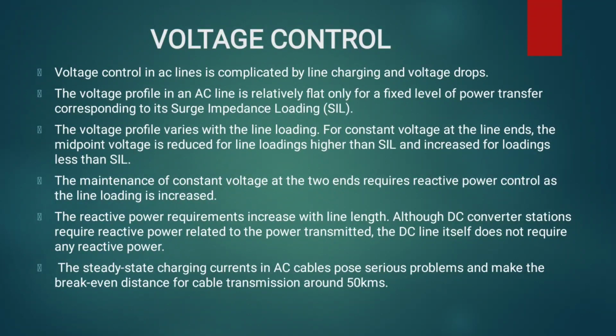And the next one is voltage control. Voltage control in an AC line is complicated by line charging and voltage drops. The voltage profile in an AC line is relatively flat only for a fixed level of power transfer corresponding to surge impedance loading. The voltage profile varies with the line loading. For constant voltage at the line ends, the midpoint voltage is reduced for line loadings higher than surge impedance loading. The maintenance of constant voltage at the two ends requires reactive power control.